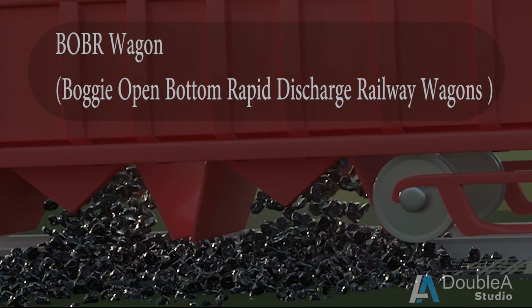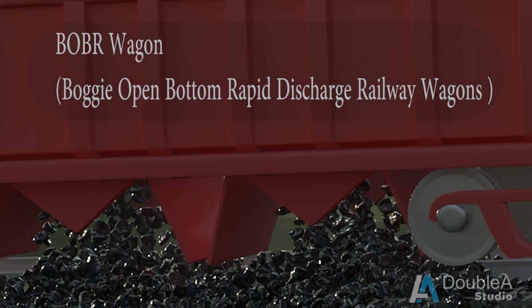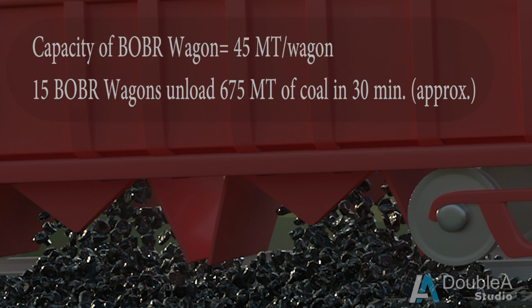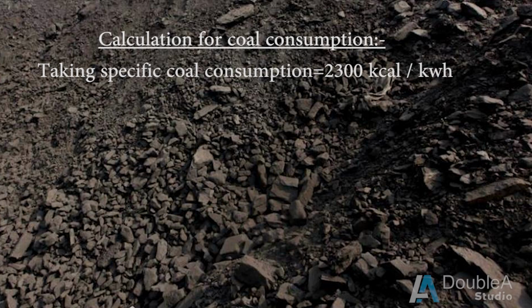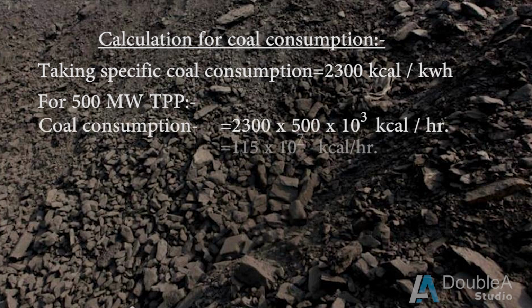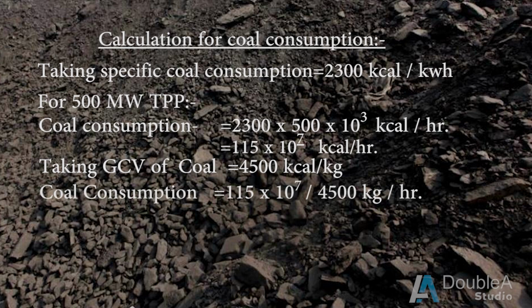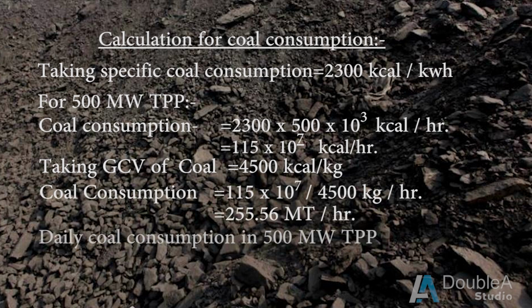That means bogie open, bottom rapid discharge railway wagons. Each BOBR wagon can carry approximately 45 metric tons of coal. Hence, each unit of track hopper carrying 15 BOBR wagons can unload 675 metric tons of coal in 30 minutes approximately. Daily requirement of coal in a 500 megawatt power plant is about 6,000 metric tons of coal, having GCV as 4,500 kilocalories per kilogram and considering heat rate of 2,300 kilocalories per kilowatt hour.